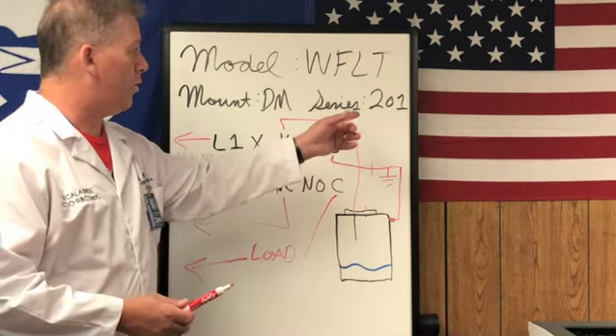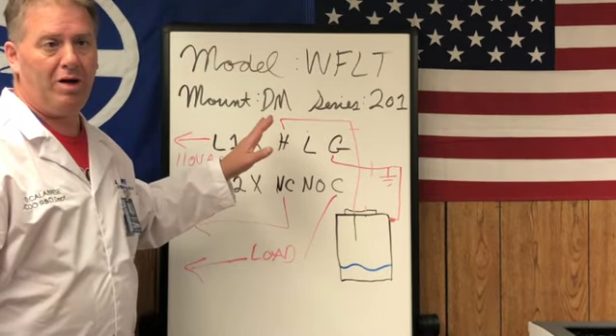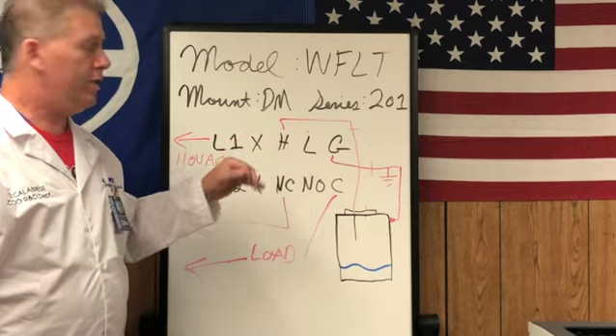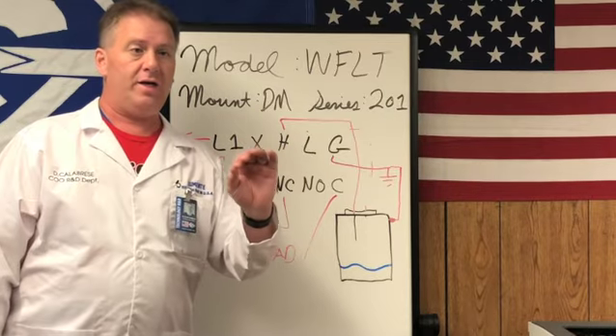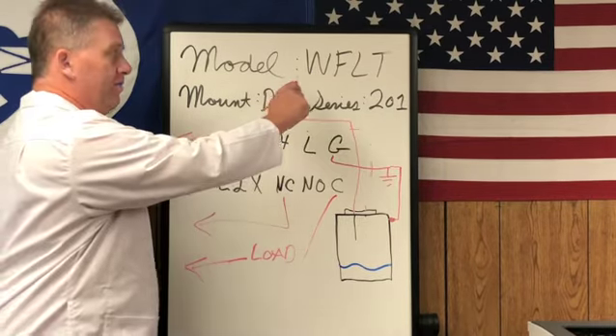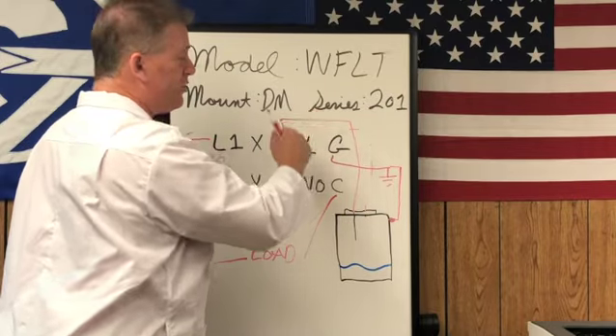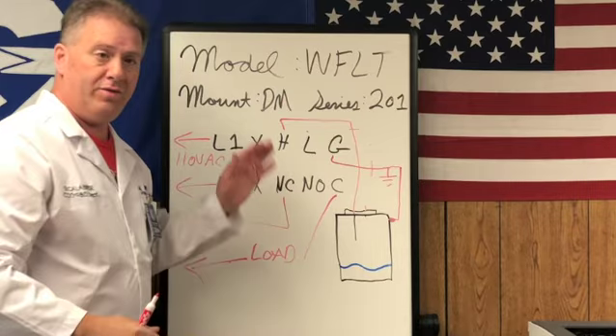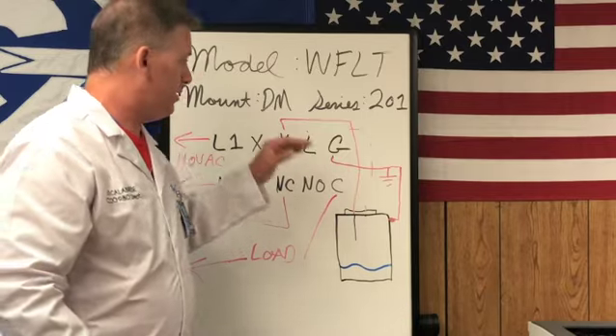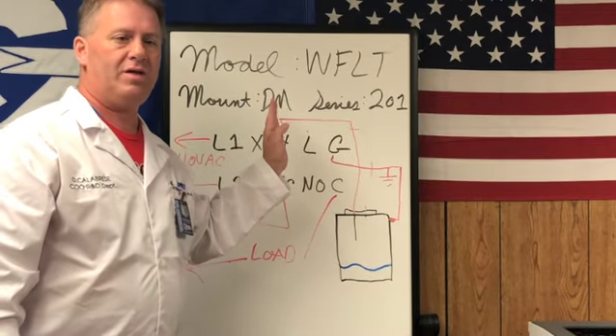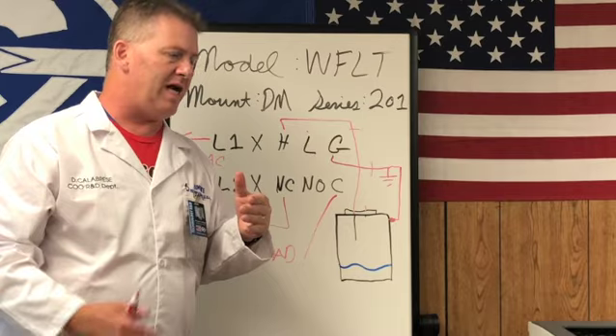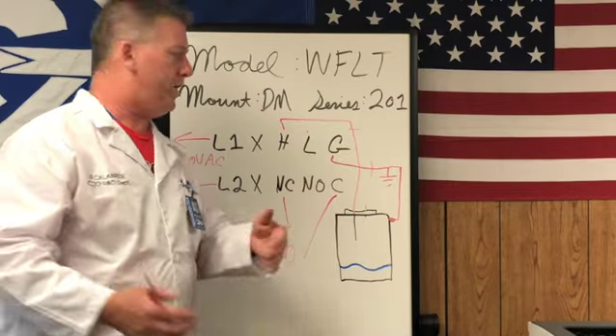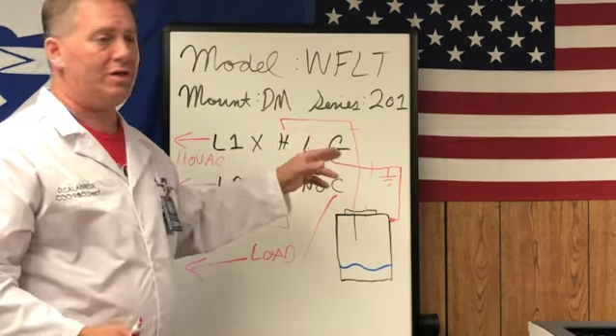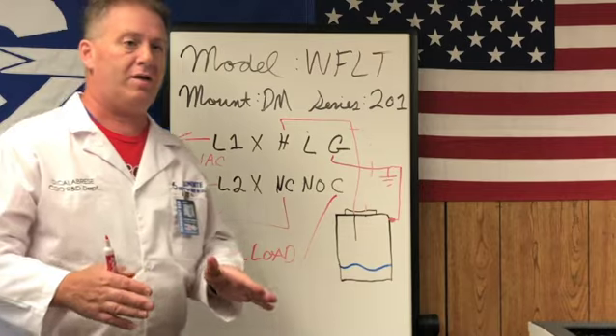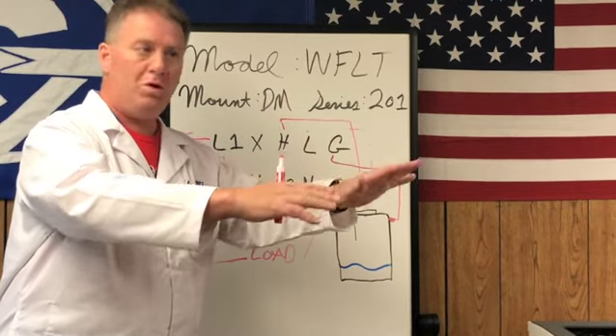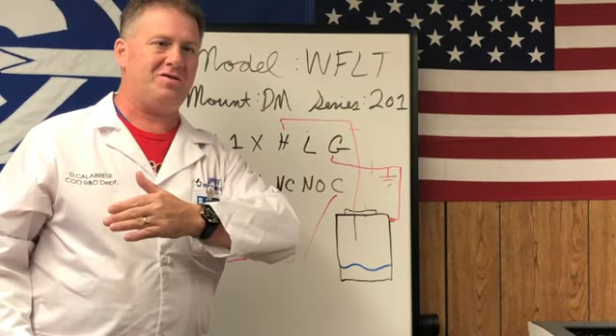Another thing with the 201, it doesn't necessarily have to be DIN rail mount. You can get it in an octal socket. You can get the 201 in a 3-inch snap track, and this is the panel level line, designated by the W. If you get the industrial level line, it would just be an FLT. Those are designed to be standalone. This DIN mount one, the panel level line, is designed for contractors and panel builders mainly to integrate into a system. The industrial level line is standalone. You can put that in a room way over there and have it control your system autonomously.